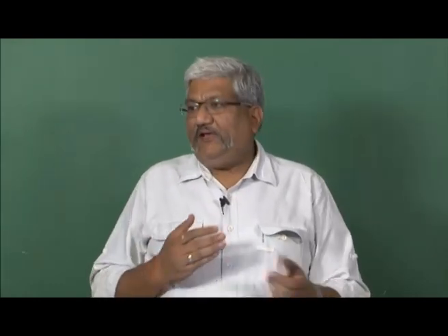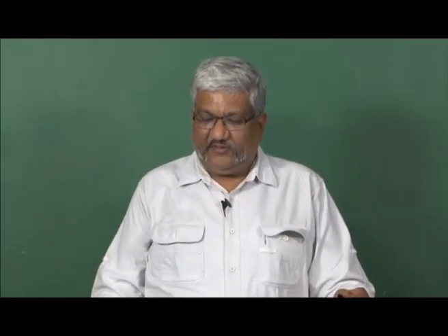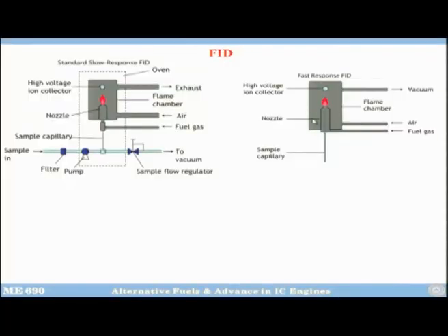But anyway, now people have come up, there is a company called Cambustion, and they have come up with this fast response FID. So, what they do is they bring this whole assembly very close to the sample point.